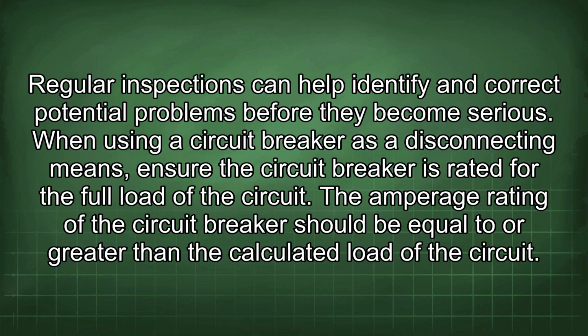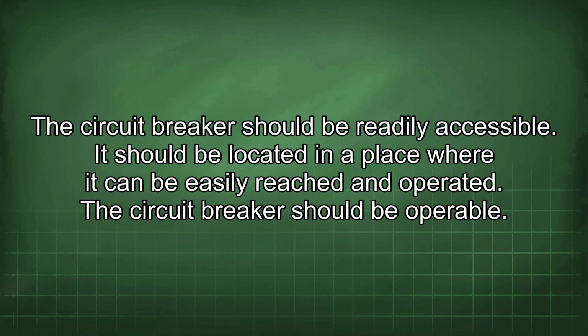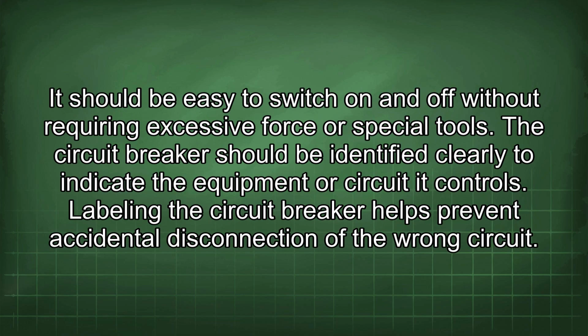When using a circuit breaker as a disconnecting means, ensure the circuit breaker is rated for the full load of the circuit. The amperage rating of the circuit breaker should be equal to or greater than the calculated load of the circuit. The circuit breaker should be readily accessible. It should be located in a place where it can be easily reached and operated. The circuit breaker should be operable. It should be easy to switch on and off without requiring excessive force or special tools.